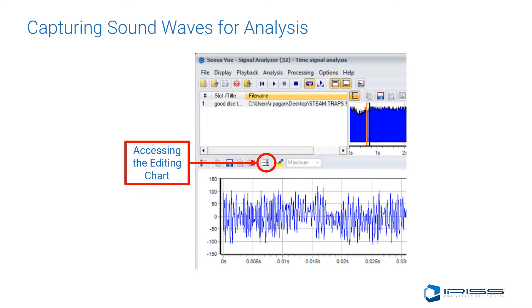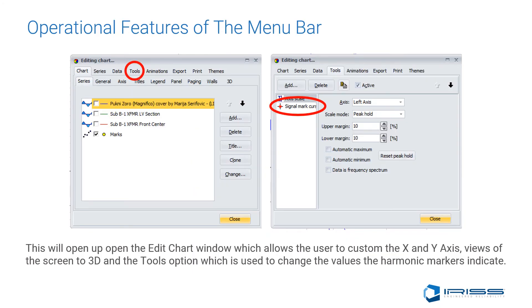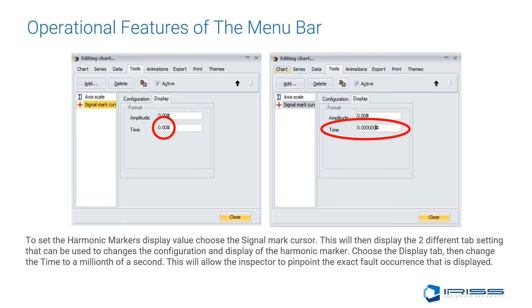To change your harmonic values, go to the editing chart axis icon located on each of the screens — whether it's the full time signal, the time waveform, or the frequency spectrum. This opens the Edit Chart window, which allows the user to customize the x and y axis, change views to 3D, and use the Tools option to change the values of the harmonic marker's value of indication. To set the harmonic marker display value, choose the Signal Mark Cursor, which displays two tab settings for changing the configuration and display.